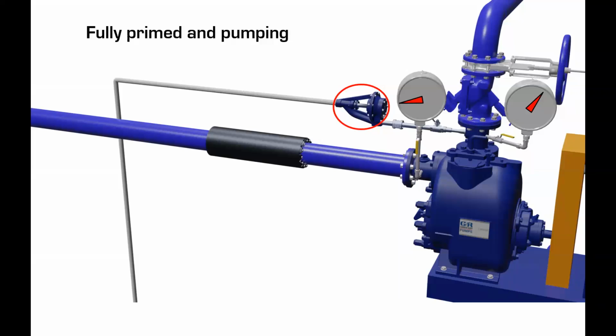And then as soon as it goes dynamic, then we pick up the friction, and that can double that lift. You know, that's when it goes a bit crazy. But you're right. When we turn off that pump again, if there's no suction leaks, then that suction gauge will lose all its friction and show the lift that we are maintaining, that static lift. Yes.